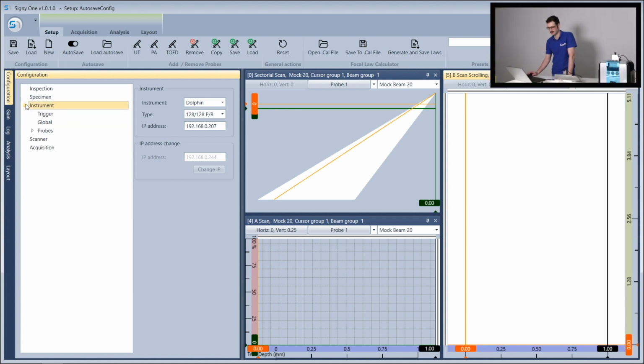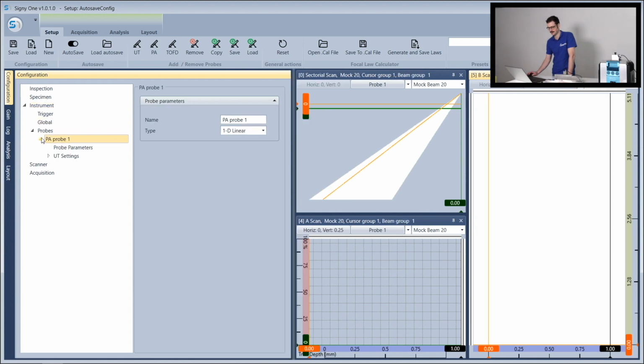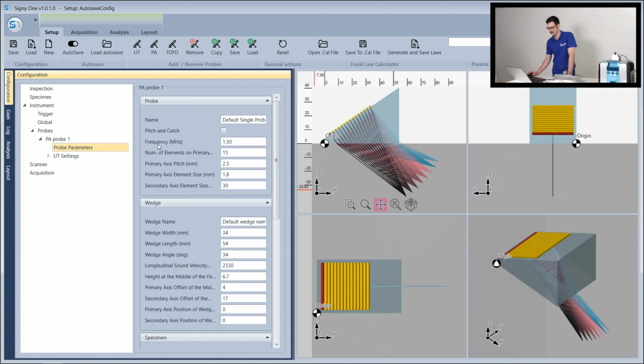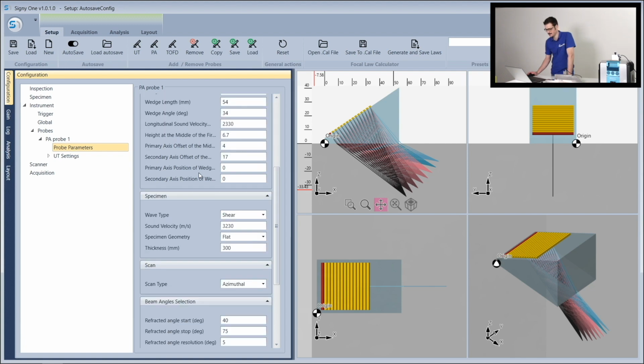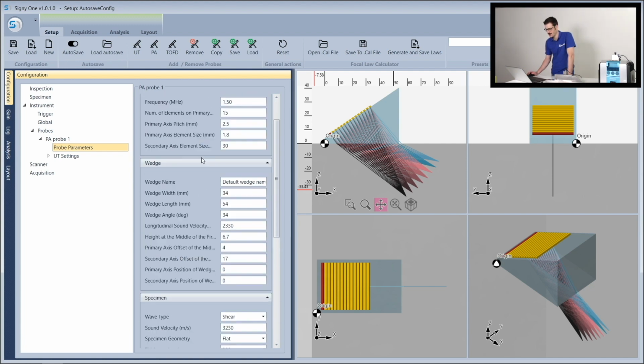I first go to Instrument, Probe, and I will set up this phased array probe with the information for our probe. Here I can input all information about the geometry of the phased array probe, or I can load a file that has been shipped together with the probe.